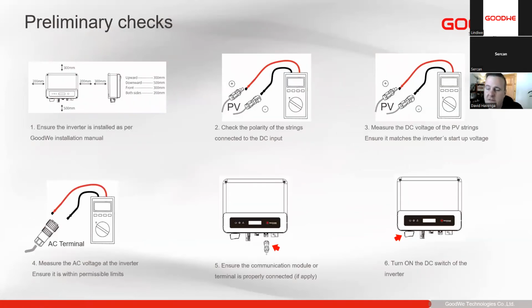So with the on-grid inverters, although our inverters do have reverse polarity protection, it's always good to make sure that your polarity is correct before connecting to your inverter. Same with the AC terminals, make sure that our terminals are well connected and the voltage and everything is there. So these are also preliminary checks, so if you're having an alarm or a fault on the inverter, always do these checks to make sure everything is okay, and then connect it up again, restart the system and see if it's working.